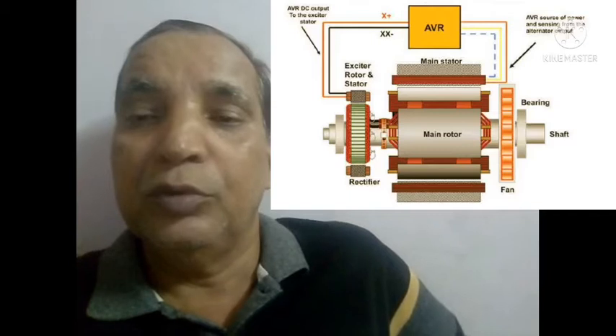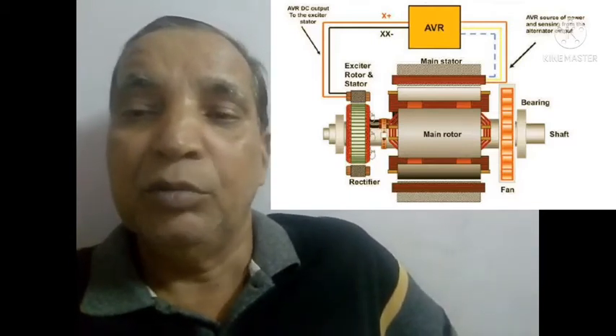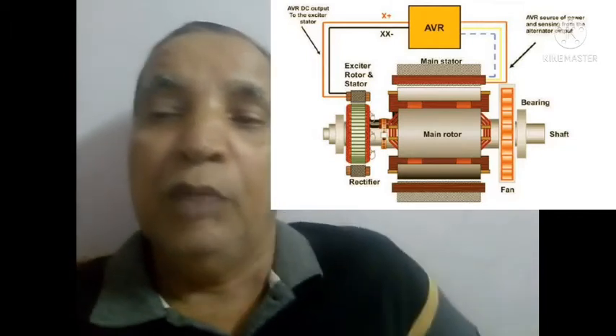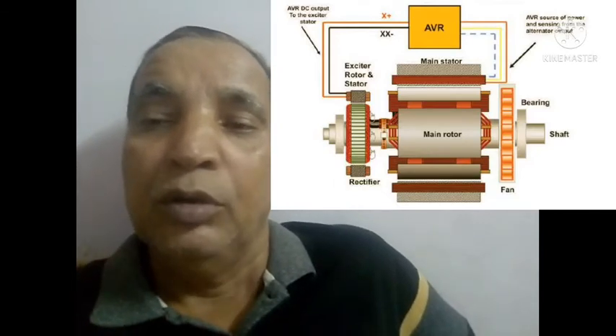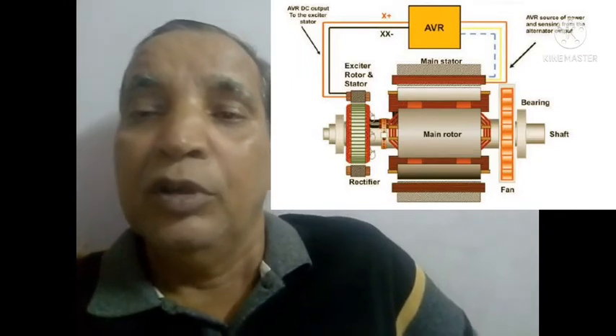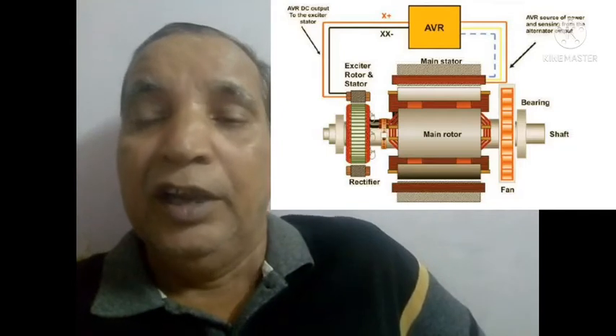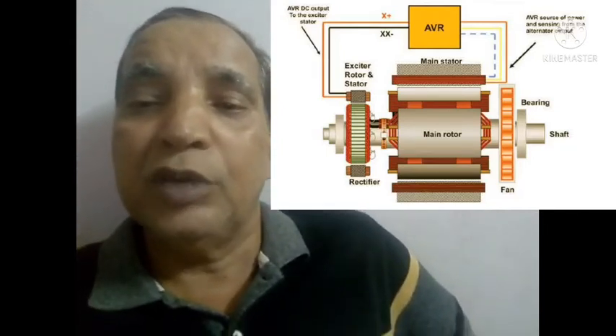This is also having the AVR as well as exciter. From alternator side, three wires are going to the AVR - two are the phase and one is the neutral. How to excite the AVR? AVR excitation through the exciter, and two wires are going to the AVR F1 F2, or somebody says X and double X.